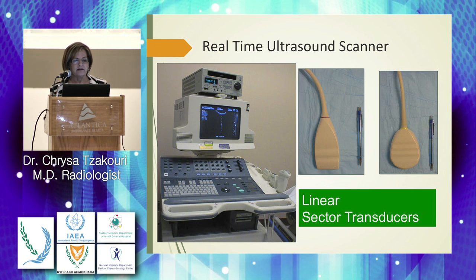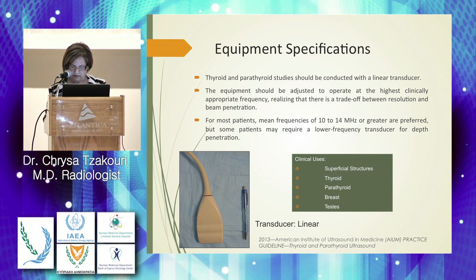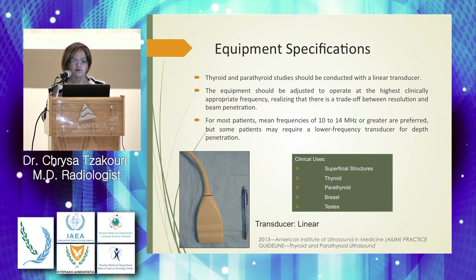Nowadays we have real-time ultrasound scanners with different transducers. According to the 2013 American Institute of Ultrasound in Medicine practice guidelines, thyroid and parathyroid studies should be conducted with a linear transducer. The equipment should be adjusted to operate at the highest clinically appropriate frequency, realizing there is a trade-off between resolution and penetration. For most patients, mean frequencies of 10 to 14 MHz are preferred, but some patients may require a lower-frequency transducer for depth penetration.